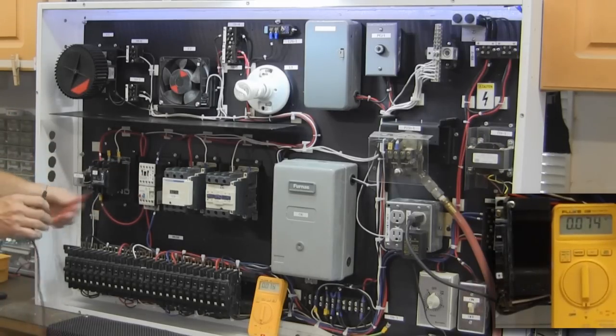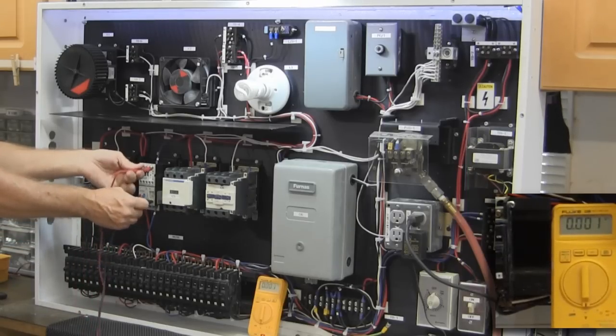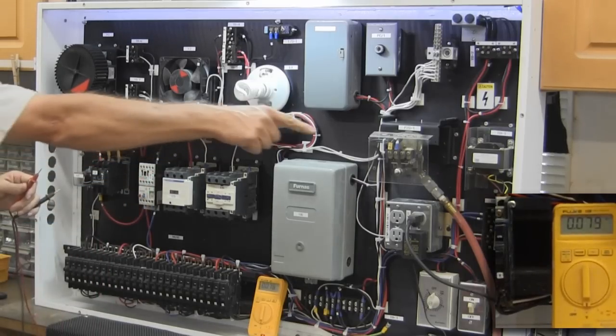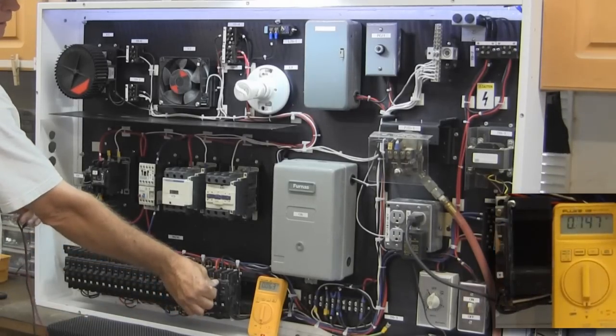This I told you is a 24 volt coil. So I'll check between the two and I'm not getting anything right now because there's no power supplied to that transformer. So we'll go ahead and turn the main power on here.